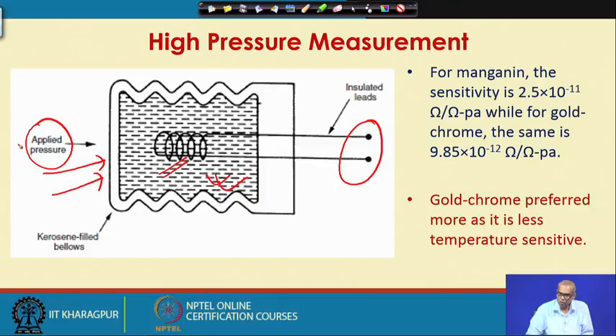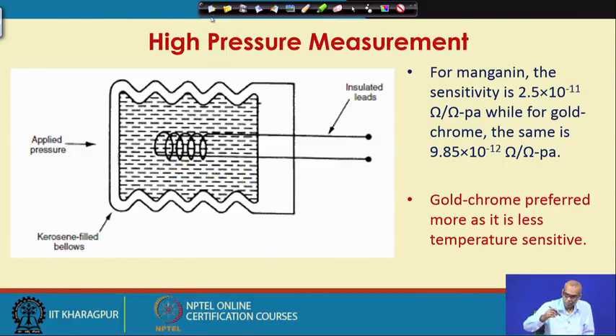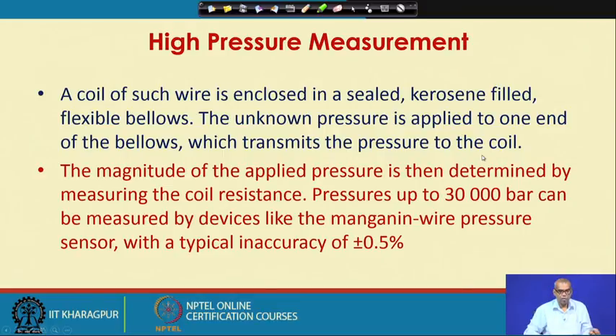For manganin, the sensitivity is 2.5 into 10 to the power minus 11, while for gold chrome the same is 9.85 into 10 to the power minus 12. Please note the unit, ohm per ohm Pascal. Gold chrome is preferred more as it is less temperature sensitive. So, a coil of such wire is enclosed in a sealed kerosene filled flexible bellows. Such wire means manganin or gold chrome alloy. The unknown pressure is applied to one end of the bellows, which transmits the pressure to the coil. The magnitude of the applied pressure is then determined by measuring the coil resistance. Pressures up to 30,000 bar can be measured by devices like the manganin wire pressure sensor with a typical inaccuracy of plus minus 0.5%.